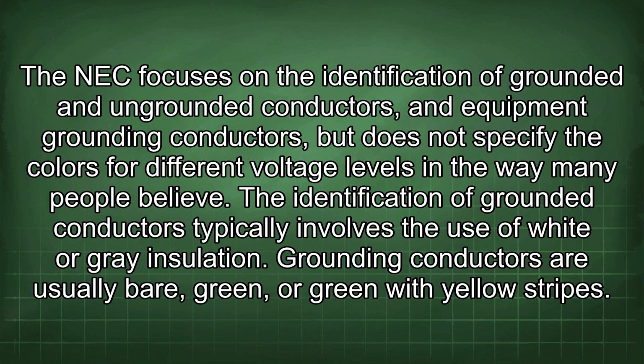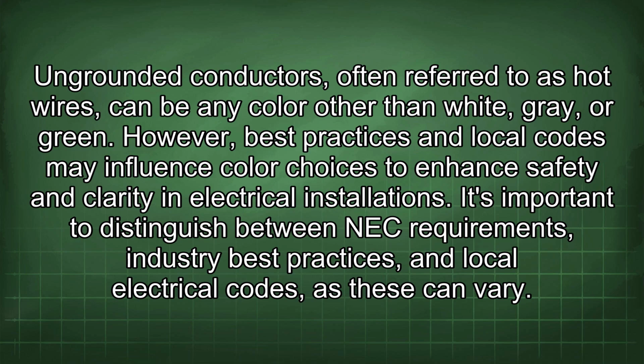The identification of grounded conductors typically involves the use of white or gray insulation. Grounding conductors are usually bare, green, or green with yellow stripes. Ungrounded conductors, often referred to as hot wires, can be any color other than white, gray, or green. However, best practices and local codes may influence color choices to enhance safety and clarity in electrical installations. It's important to distinguish between NEC requirements, industry best practices, and local electrical codes, as these can vary.